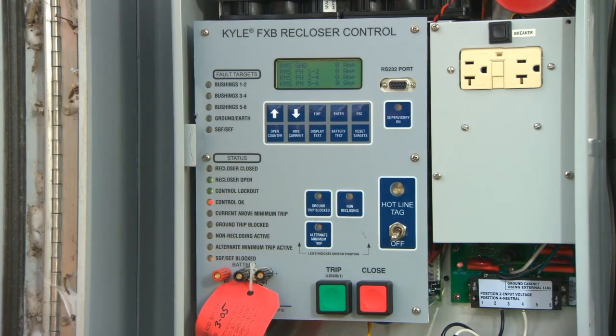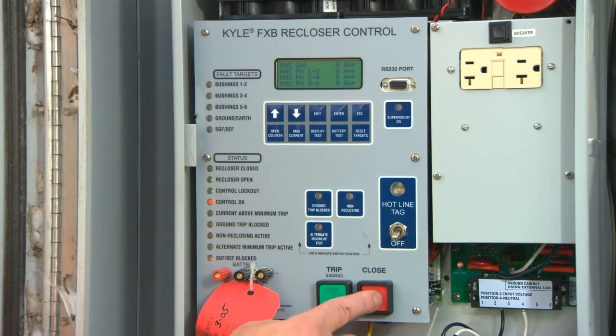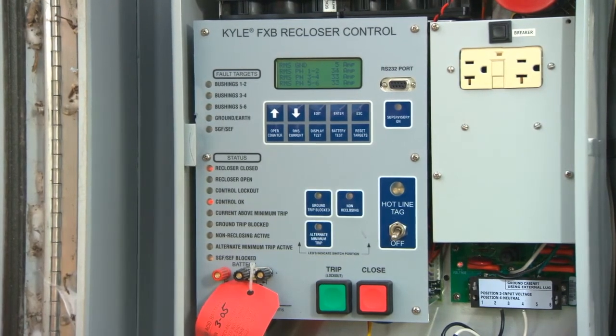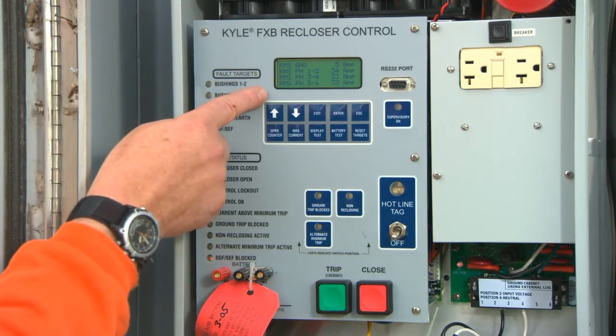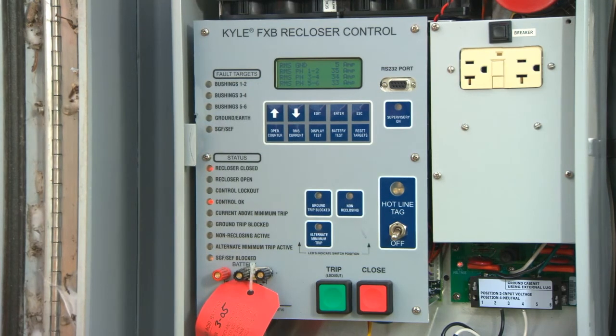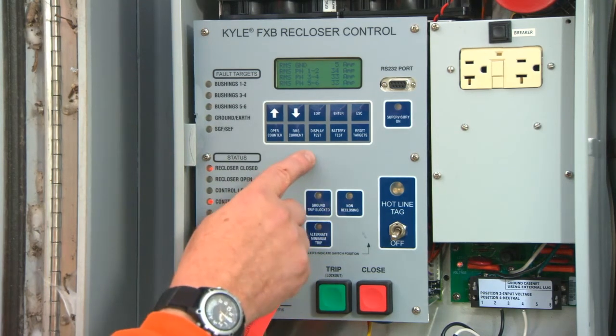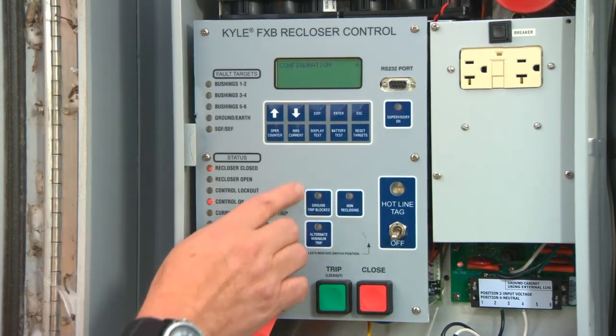If your source and load side leads are installed and the reclosers are open, you should have no current going through it. With the bypass switch still closed, press the Close button to close the recloser. You will notice on the display that a percentage of the amperage is now going through the recloser, as well as a percentage through the bypass switch. The display now shows verification that we have amperage on all 3 phases. It is now safe to open the bypass switch. Approximately 1/4 to 1/3 of the amperage should flow through the recloser. Now, press Escape to return to the main menu.